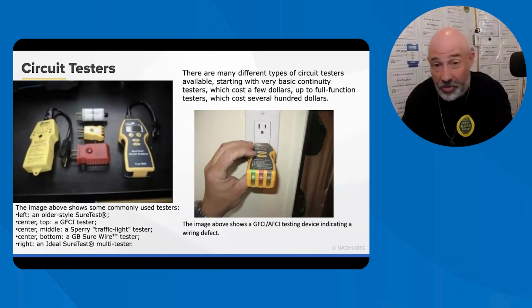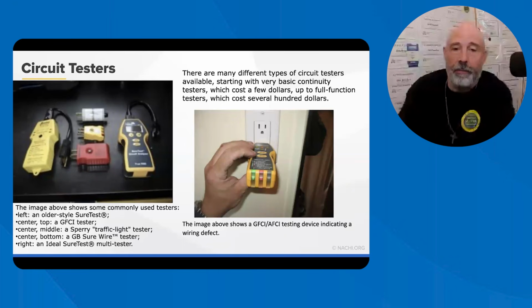Matter of fact, I went to a new house yesterday, and they actually had reversed polarity on it. So the typical function of some of these testers, a lot of times I use the cheapest tester I possibly can. We're there to just make sure they're working. I'm not going to check every single one for 120 volts or 115 volts. I just want to check them all, and then I want to make sure that the GFCIs are tripping. That's pretty much it.